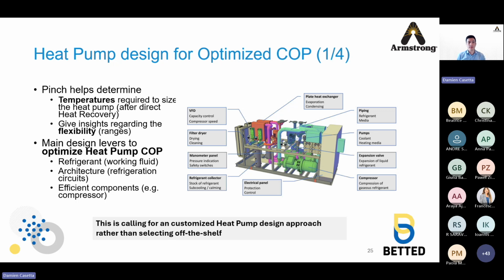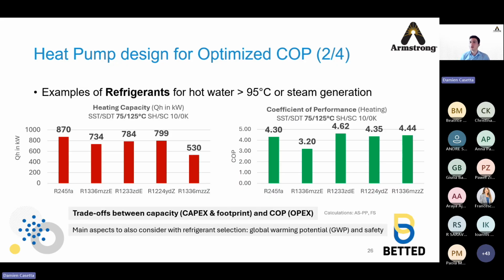So what's the takeaway here? The takeaway is to use pinch as the input to the heat pump design and customize the heat pump to maximize the COP rather than taking off-the-shelf equipment. Optimizing COP means selecting the right refrigerants. Here are a few examples of refrigerants that can address hot water needs above 95 degrees or steam generation. So you have those names on the screen. I won't list them all.